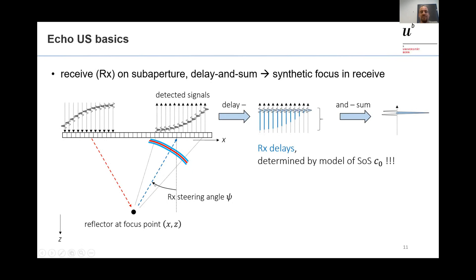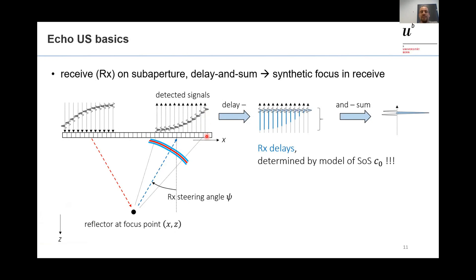A sub-aperture of the array detects on each piezoelectric element individually a voltage signal. Whereas we use physical focusing on transmit, on reception we just acquire the signals and do the focusing in software. All signals are delayed relative to each other so that a signal coming from the focus will line up in time across the different elements, and then the sum is performed. This is the famous delay-and-sum algorithm. The receive delays are also calculated based on the assumed speed of sound C0.